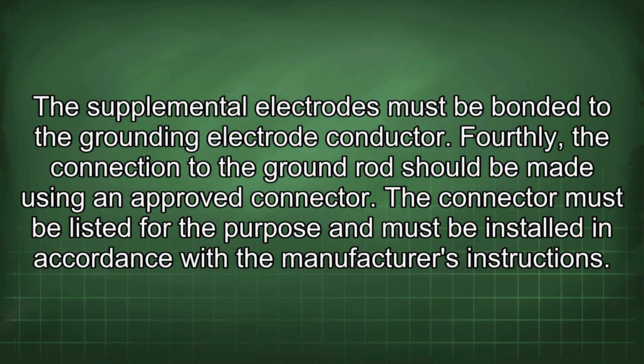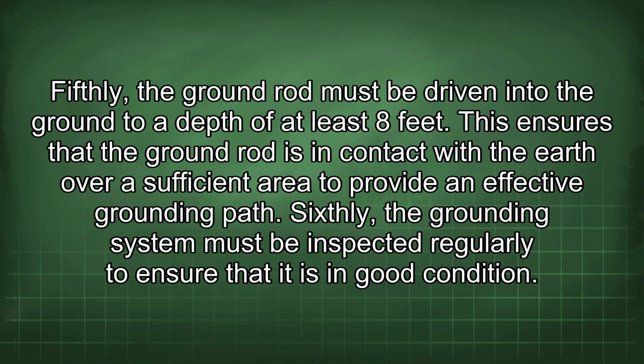Fourthly, the connection to the ground rod should be made using an approved connector. The connector must be listed for the purpose and must be installed in accordance with the manufacturer's instructions. Fifthly, the ground rod must be driven into the ground to a depth of at least 8 feet. This ensures that the ground rod is in contact with the earth over a sufficient area to provide an effective grounding path.